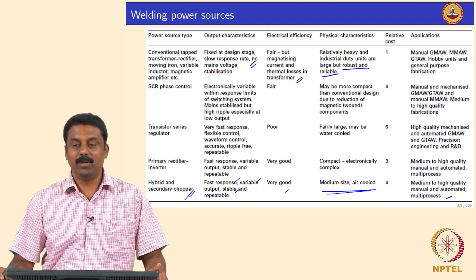You see this point that John Norris mentioned: robust and reliable. You won't see one diode bursting because there are no diodes. In our case, for example, if one capacitor goes away in a primary rectifier inverter system, you have to replace the capacitor, and that will be close to 1/3 of the cost of the power source itself. Whereas in a conventional tap transformer, what could go wrong? The transformer is there, the rectifier, that's it. It will work like a robot.